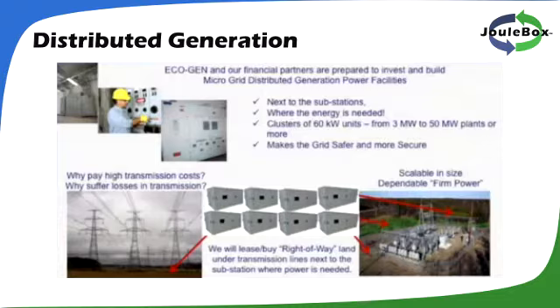By positioning JouleBox power plants next to substations, we avoid all the expense and losses associated with high-voltage transmission lines. We can provide firm, baseload power 24/7, 365 to the substation, where it can be delivered at medium voltage through distribution lines. These plants can be sized from 3 megawatts to 50 megawatts each.